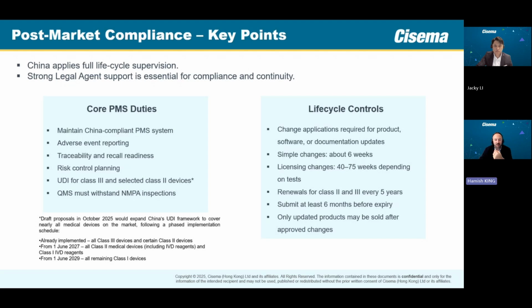UDIs are now required, so there are continual changes even for ongoing or in-market products, and these controls are important to maintain and be aware about. As part of your certificate management, you'll also need to consider whether product changes are required, because an approval change where there's a major change can take 12 months or more. So that's something that really needs to be planned in advance, and that's where drafting the PTR is important, because if there's a change in the PTR, this will usually trigger an approval change.